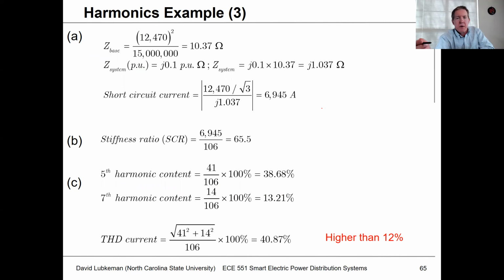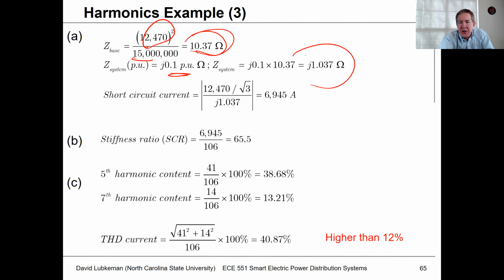All right, so get my pen out. Okay, so for a 12.47 kV system, we've got a 15 MVA source. This gives us the base value. If I've got this impedance in per unit, I can multiply by the base value, and this gives me this value in ohms. The short circuit current I would have at this bus would be the line-to-neutral voltage divided by the impedance, and so the short circuit current is 6,945 amps.